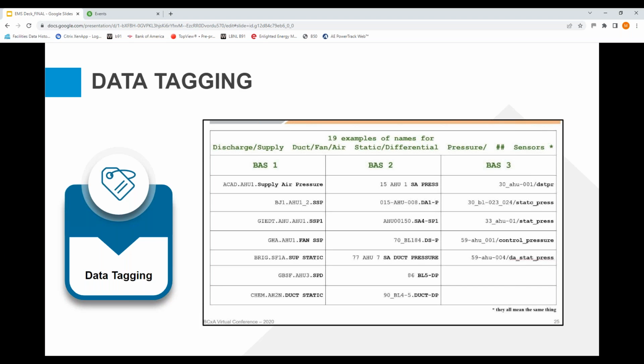One more example regarding data tagging: two of the systems being integrated today on a regular basis are HVAC and the lighting system. Part of the reason is we're using the lighting system to actually control the HVAC for an energy efficiency measure. We take the occupancy sensors, so in a conference room, if nobody's using it and the occupancy sensor says it's vacant, we can turn the ventilation air off or down to a lower set point, and let the temperature set points drift a bit, making a wider band. So that room might get a little hotter or colder than if it were occupied, and that saves energy.